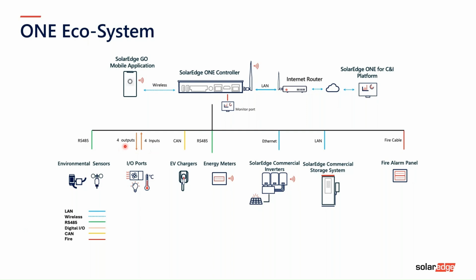We then got the 4 outputs. These are on-off devices. Currently, one of these is used for the firefighter gateway feature. We are going to have another released fairly soon for the generator, similar to the power reduction interface, but unlike that, which drops the power, this will switch to safe DC mode. So we'll have 2 options there, and another 2 outputs we can use to turn things on and off.